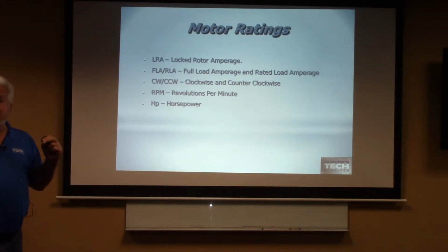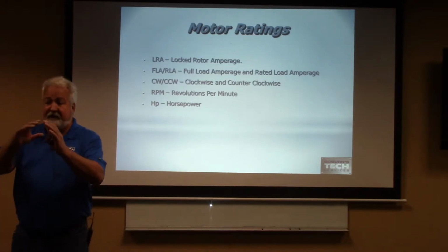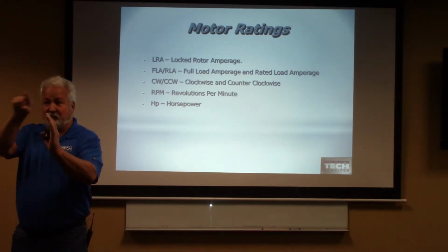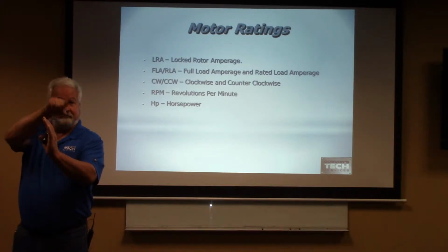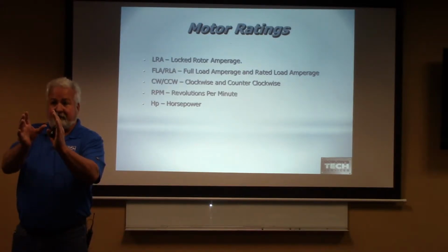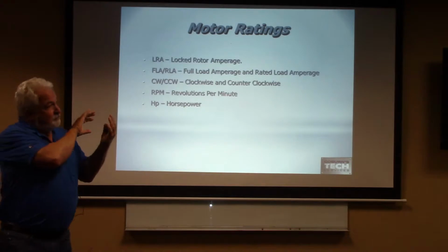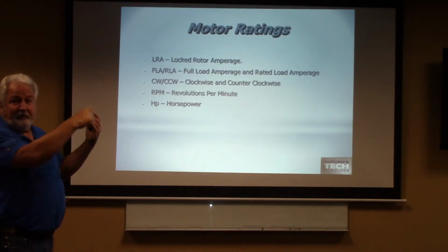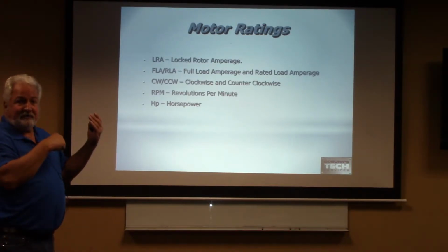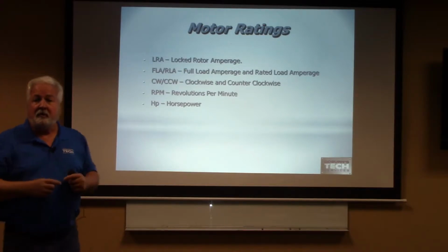I need to pay attention to whether it's clockwise from the lead end of the motor, where the leads come out, or clockwise from the shaft end of the motor. Some manufacturers still rate shaft ends. Most of them rate at the lead end of a motor. If I'm looking at the lead end of a motor and it's turning this way, it's clockwise. If I'm looking at the shaft end of that motor and it's turning that way, it's counterclockwise. Does that make sense? Good.